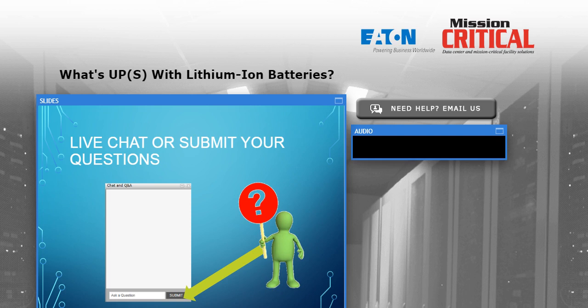Okay, let's see. A lot of questions coming in. Can you install lithium batteries in the same room as flooded lead acid batteries? Another excellent question. I myself didn't see this as being a possible issue, but in looking at the fire code requirements, that is one thing that they are very strict about. If you have multiple battery chemistries existing in the same physical room, there are much stricter limits, much lower limits on how much battery you can have.